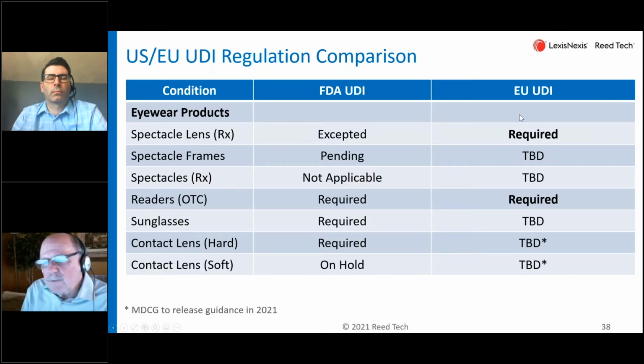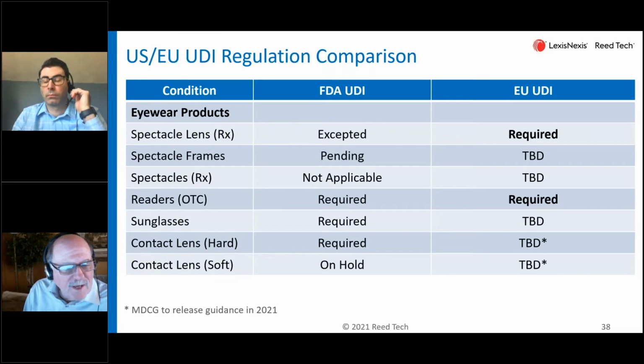If you do the comparison to the European Union, there was a guidance that came out previously, and it explicitly mentioned spectacle lens and the ready readers, as I refer to them, are actually required. So that's quite different for the spectacle lens. So the US, where you did enjoy an exception, now they are required to have UDI. So that's quite a change in policy and what you need to prepare for. The other to be decided, there's some reference to a guidance hopefully coming out later this year, supposedly in 2021, that addresses some of these issues about these other product codes. So we're waiting to hear that for sure about where they stand. We'll have to find out if the European Union is including some of these, or if some exceptions would apply. Again, just don't know yet, but as we find out, we'll pass that information on to you.